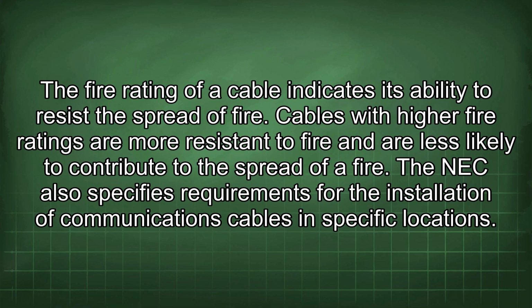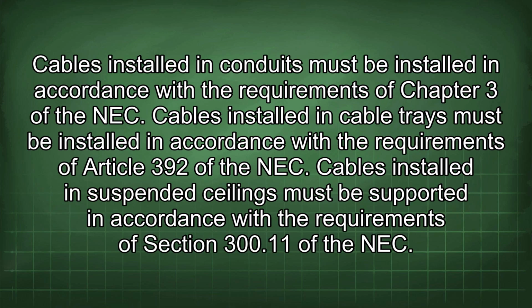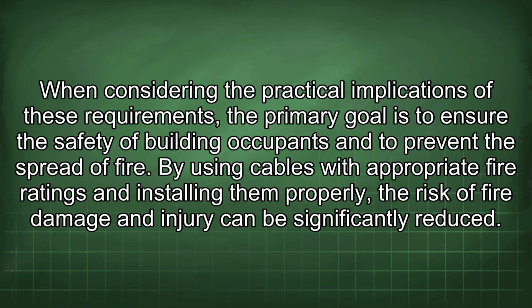The NEC also specifies requirements for the installation of communications cables in specific locations. Cables installed in conduits must be installed in accordance with the requirements of Chapter 3 of the NEC. Cables installed in cable trays must be installed in accordance with the requirements of Article 392 of the NEC. Cables installed in suspended ceilings must be supported in accordance with the requirements of Section 300.11 of the NEC. When considering the practical implications of these requirements, the primary goal is to ensure the safety of building occupants and to prevent the spread of fire. By using cables with appropriate fire ratings and installing them properly, the risk of fire damage and injury can be significantly reduced.